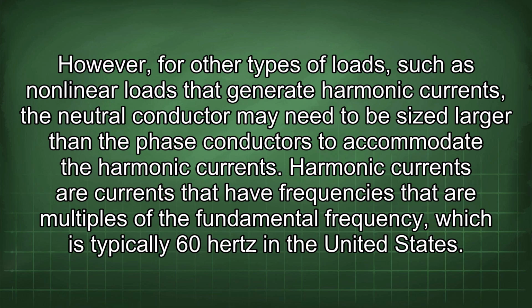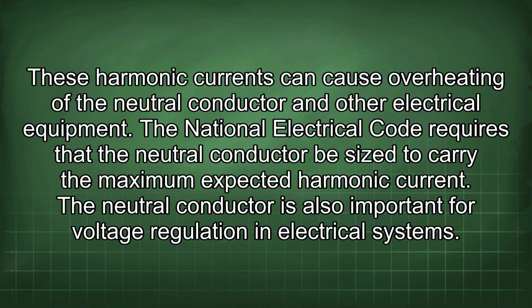Harmonic currents are currents that have frequencies that are multiples of the fundamental frequency, which is typically 60 Hz in the United States. These harmonic currents can cause overheating of the neutral conductor and other electrical equipment. The National Electrical Code requires that the neutral conductor be sized to carry the maximum expected harmonic current.